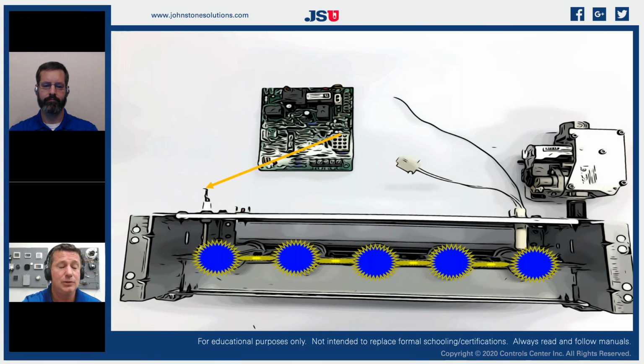We are going to now apply electrons directly into that flame. So we're going to use an orange wire. Most manufacturers use an orange wire for their flame sensor. It's not a sensor, it's a rod. That's all it is, a rod. We are going to apply electrons into that flame, and we're going to add a dedicated ground onto that circuit. And we are going to pass electrons from our control board through the flame back through ground.